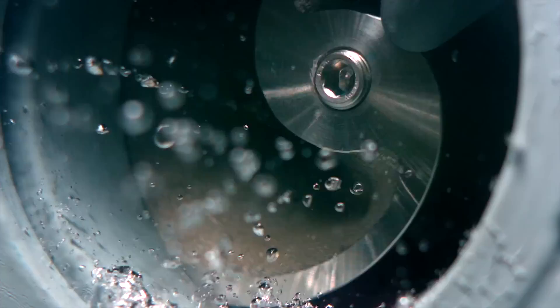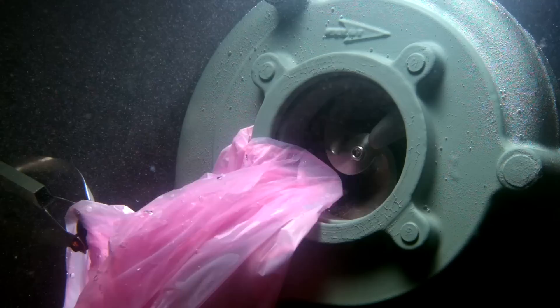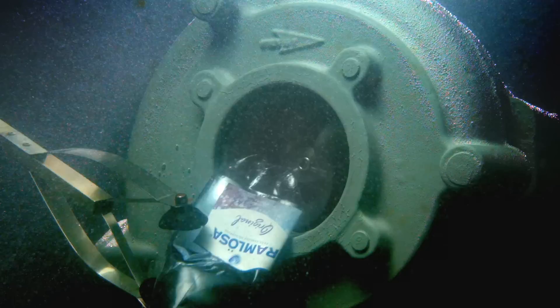Now we will show how we can sustain that efficiency even when many objects are passed through the pump — including a plastic bag, a diaper, plastic bottles (first one, then five, then eight), and T-shirts. This is where many pumps get into trouble.